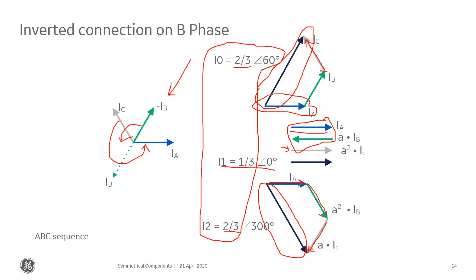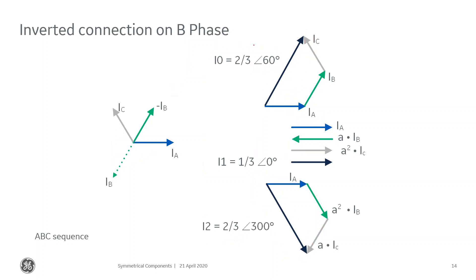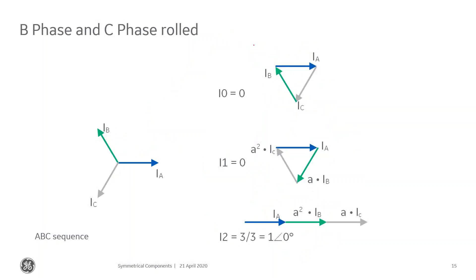One of the things we should always do when commissioning protective relays or meters is look at the positive, negative, and zero sequence components from our metered quantities to verify we've eliminated wiring errors. This can immediately point out a wiring error — though then you have to figure out what that wiring error is.